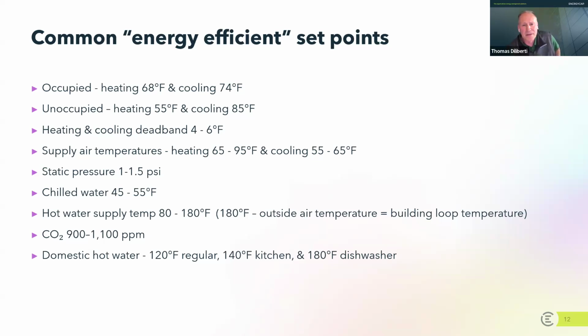Hot water supply. I want to teach you a little bit about this. The hot water supply for a building should vary depending upon how cold it is outside. There's a formula in the industry, if you haven't seen this before, where you take 180 degrees and subtract the outside temperature, and that will tell you what your building loop temperature should be. Let me give you a scenario. Let's say you're in the north. I live in Michigan. So let's say it's a winter day in Michigan where the outside temperature is 30 degrees. The way most buildings are designed, you take 180 minus the 30 and come up with 150. So 150 degrees is what the building loop temperature should be. Most of the systems are designed to take that 150-degree water, and there's enough heat in that to heat the building. This rule, 180 degrees minus the outside air temperature, is very common throughout the industry, and you should be aware of that as you're evaluating your building automation system, just to see how the numbers check out.